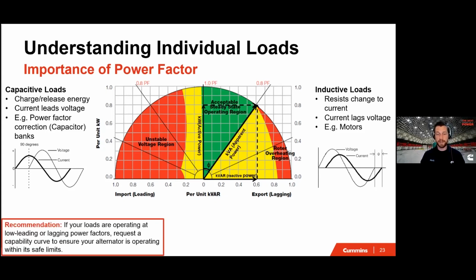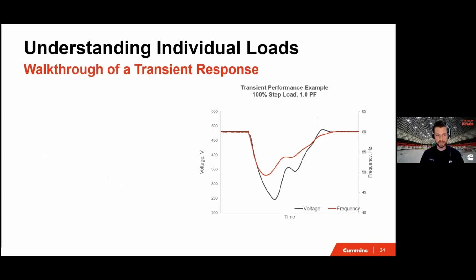So ultimately, that primer on leading and lagging power factors leads us to this watch out for your consideration. Be mindful of the overall system power factor and absolutely consult your generator set manufacturer if you have any concerns. We can work with you to provide a gut check if the alternator selected can handle the job or not. I touched on this in the prior slide, but I'll go into more detail here.